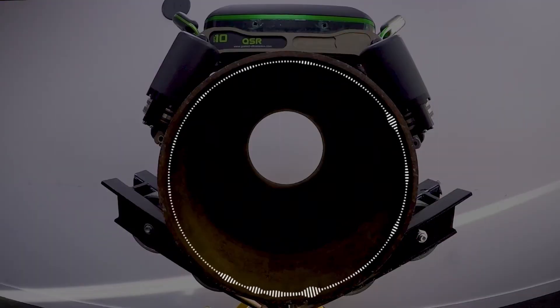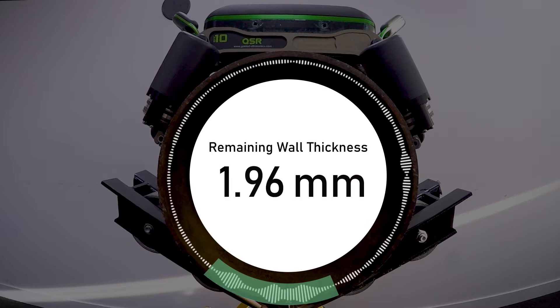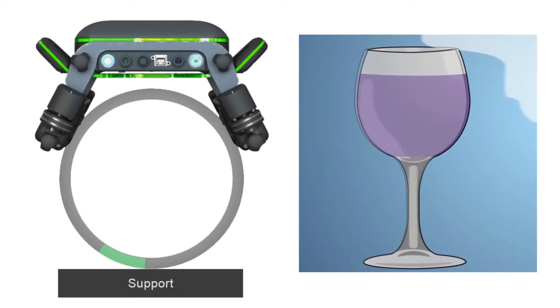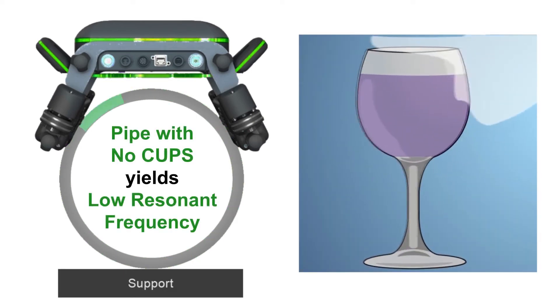The QSR1 uses circumferential guided waves and a frequency-based analysis method for accurate corrosion sizing. GUL scanning's frequency-based method for corrosion sizing is analogous to the concept of resonant frequency of a water-filled glass.